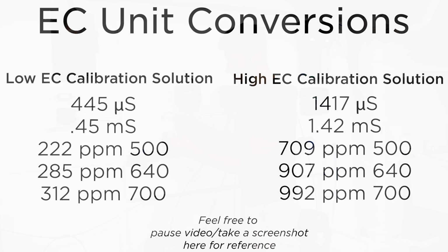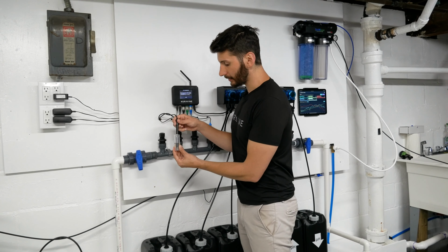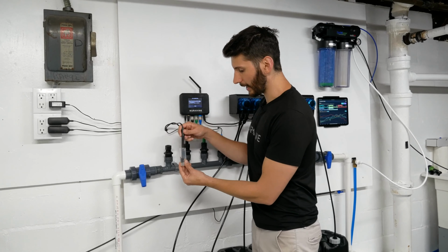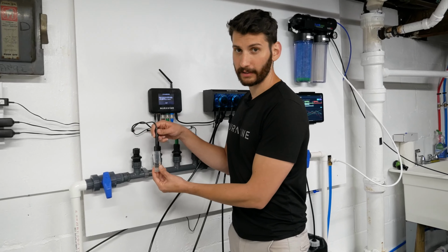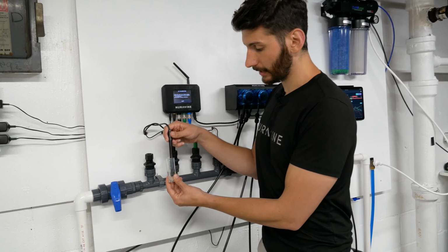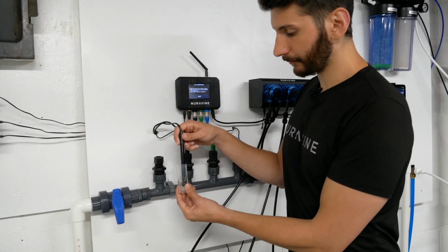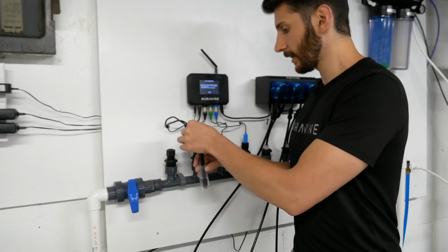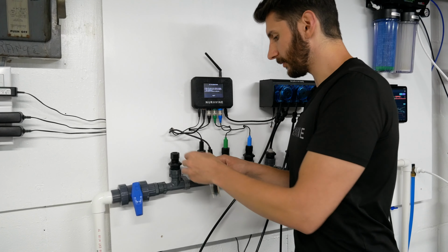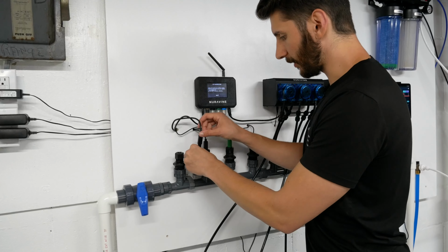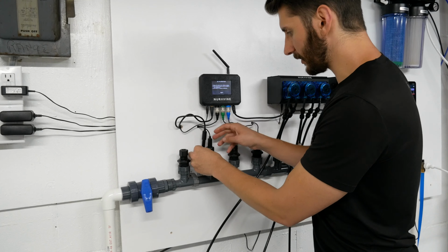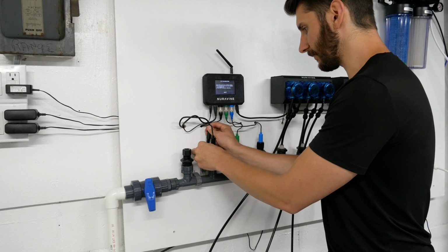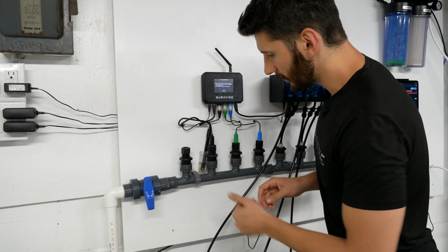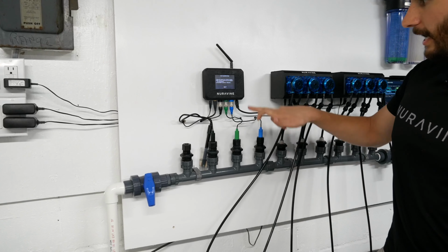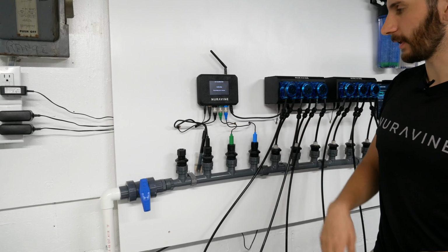Okay, so now I'm placing the probe into the bottle, and I'm going to shake it around because remember, water can get stuck in there, but so can air. So you want to make sure that it gets all the air out and that it's really in the solution. Now what I like to do if I have the manifold is rest the bottle like this. That way it's a little bit easier, so you don't always have to be holding the calibration bottle. So I've jammed it right in there. And now I'm going to push next to perform the calibration.